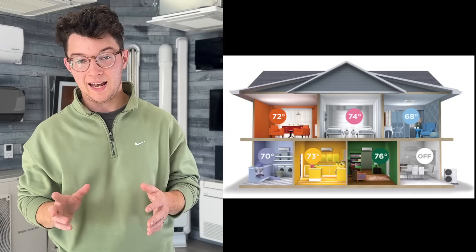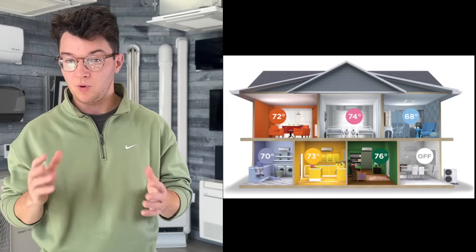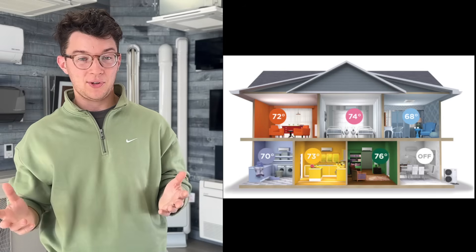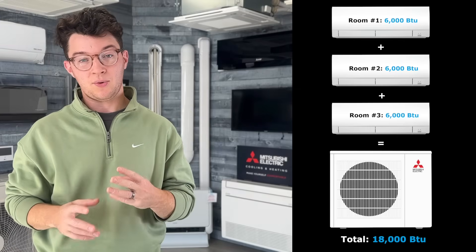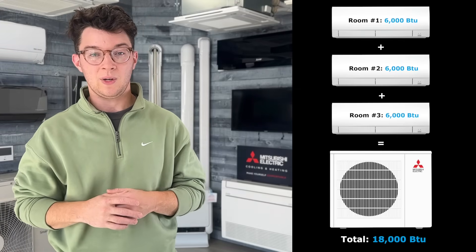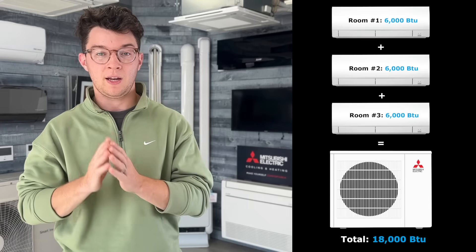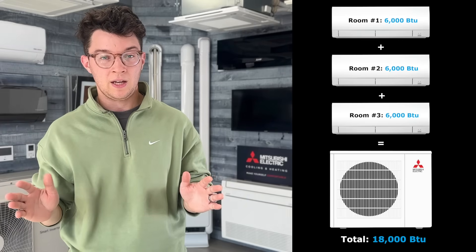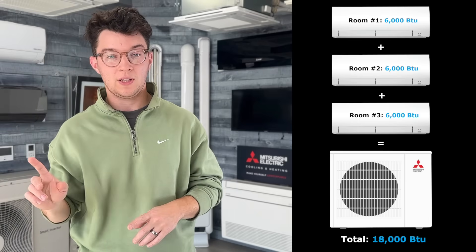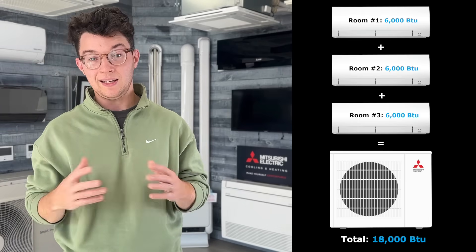Sizing a single room is fairly simple — if you have an 18,000 BTU indoor unit, your outdoor unit is also going to be 18,000 BTUs. Now, what if you want to connect multiple indoor units for multiple rooms to one outdoor unit? You start by sizing the indoor units and then add up those calculations to determine the outdoor unit size. For example, if you have three bedrooms and each bedroom requires a 6,000 BTU indoor unit, you add all three together and get 18,000 BTUs total.